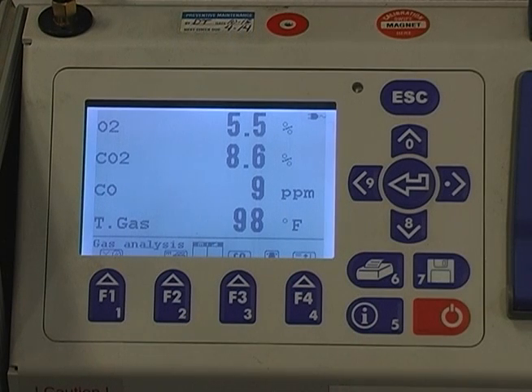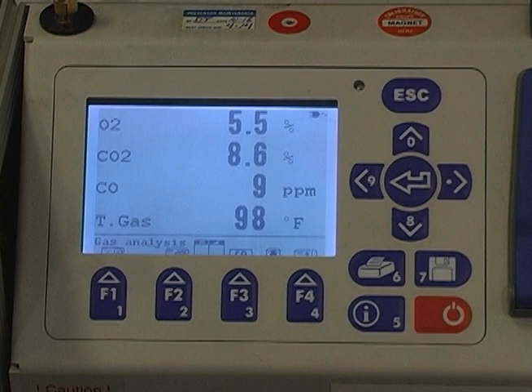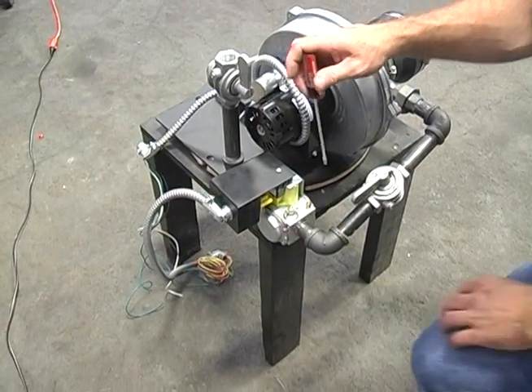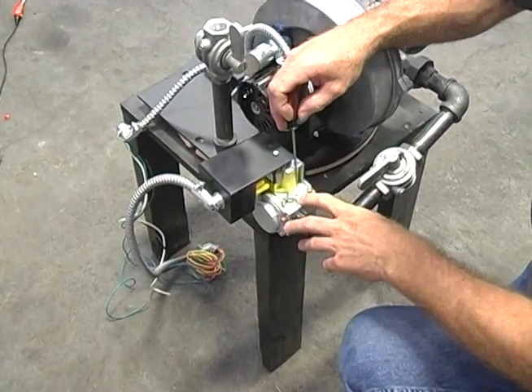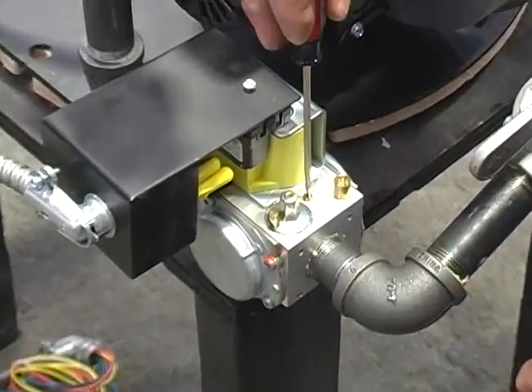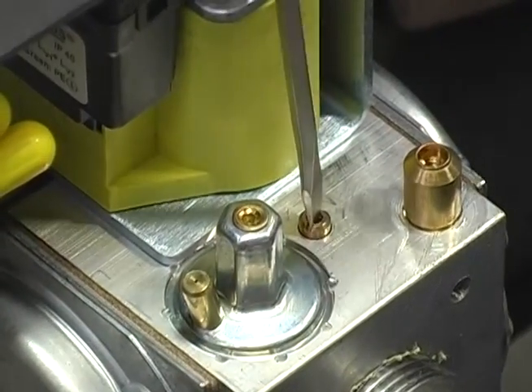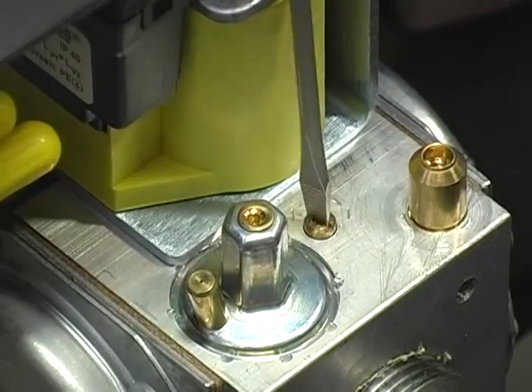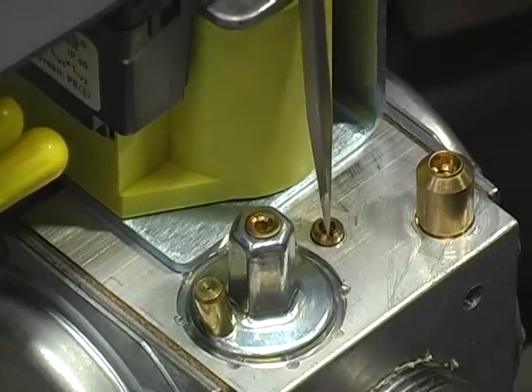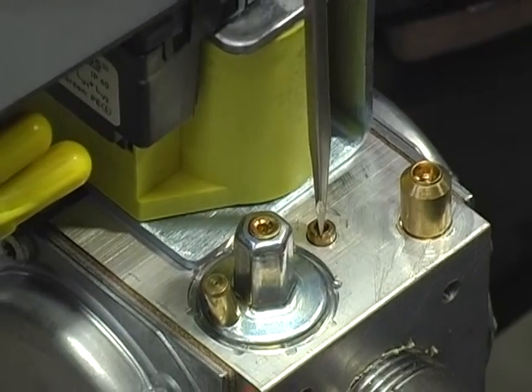Carbon dioxide level must be between 8.5% and 9.5% for natural gas, and between 9.5% and 10.5% for LP gas. If the level is in this range, no adjustment is required or recommended. If the level must be adjusted, this is done by turning the slotted brass start gas setting screw on the gas valve. Turn the screw clockwise to decrease gas flow and decrease CO2. Turn the screw counterclockwise to increase gas flow and increase CO2.